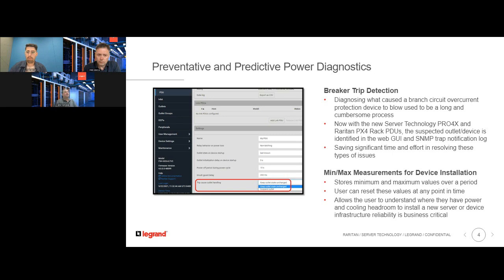Well, it can. So we're looking at two different things really on the current. We're looking at the branch current, because you don't want to get close to the usually 20 amp max rating on the branch. So we can alert before you would overload the branch. We can alert that you've had a branch current breaker fail. We could also look at the current overall for the overall capacity of the rack by monitoring at the infeed of the PDU as well. And we can do waveform captures there as well.